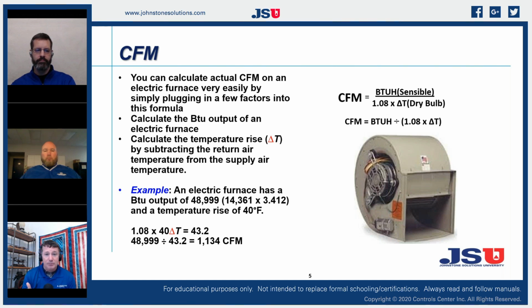I don't have to put a vane tool on that to measure how much airflow is coming through my duct system. I've actually calculated what my CFM is on that thing. If I didn't have a manometer and I had an actual static pressure versus CFM chart on my piece of equipment, I now know what my static pressure is on my system without putting probes on a thing. Simply using my meter and some temperature probes, I can calculate what my actual CFM is.